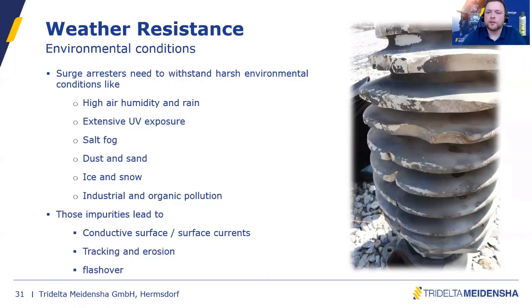Okay, coming to another topic, which is important for the design and the selection of the surge arrester. The topic is weather resistance. I chose this headline because there are many things to consider, especially when it comes to demanding environmental conditions, like regions with high air humidity and rain, what we understand as tropic areas. We have extensive UV light exposure, like in the desert. We have salt fog, like in coastal areas, dust and sand. Especially a sandstorm is a very critical thing when porcelain housed surge arresters are used, because it's like sand blasting to the housing of the surge arrester.